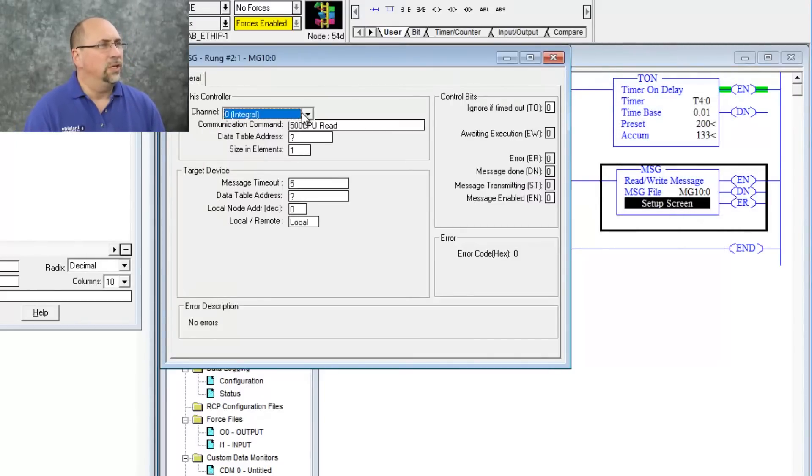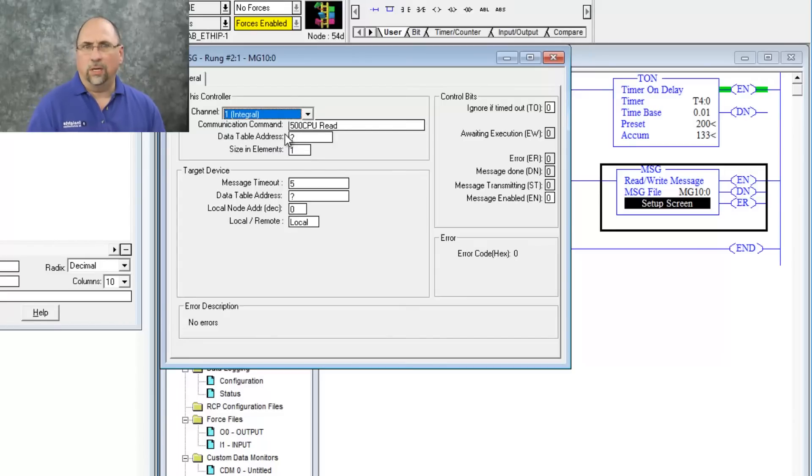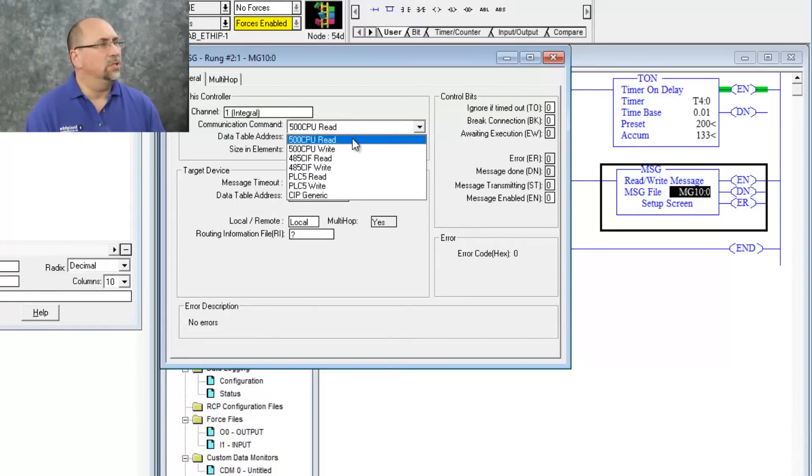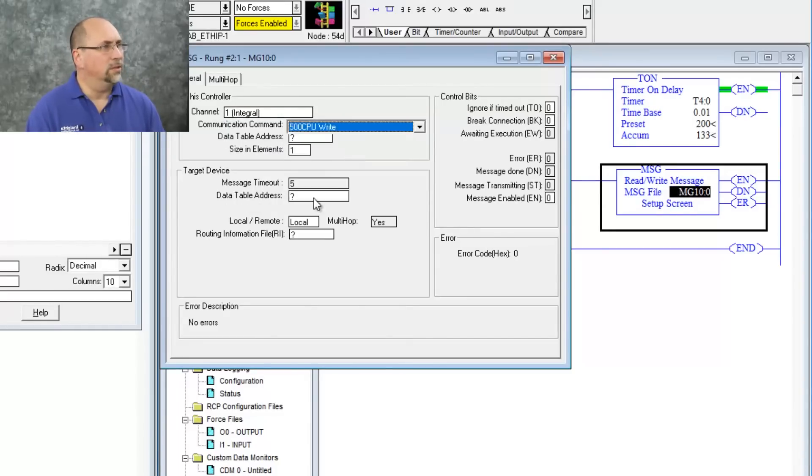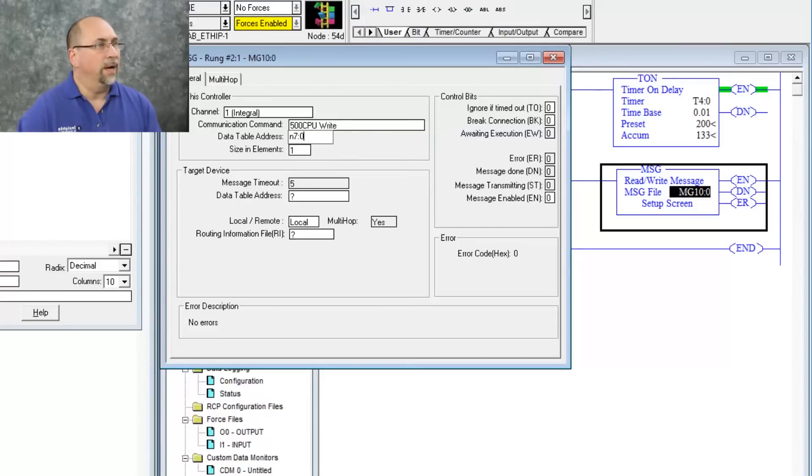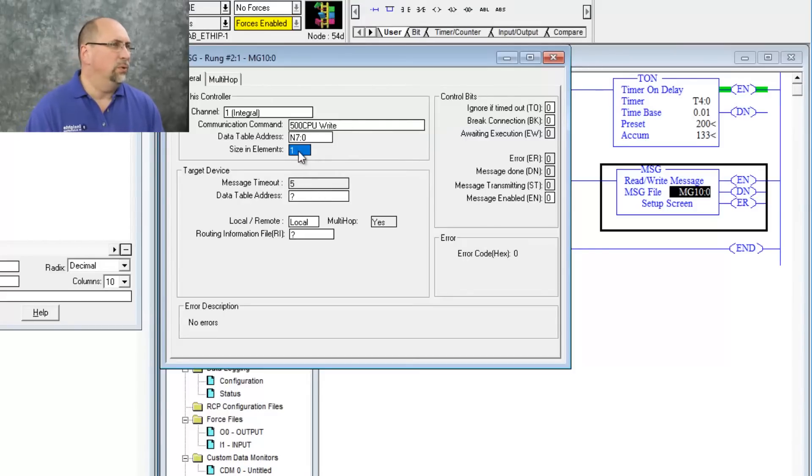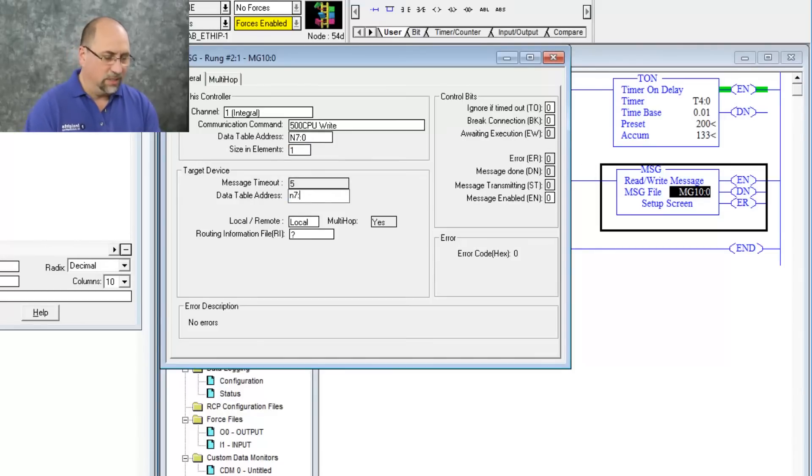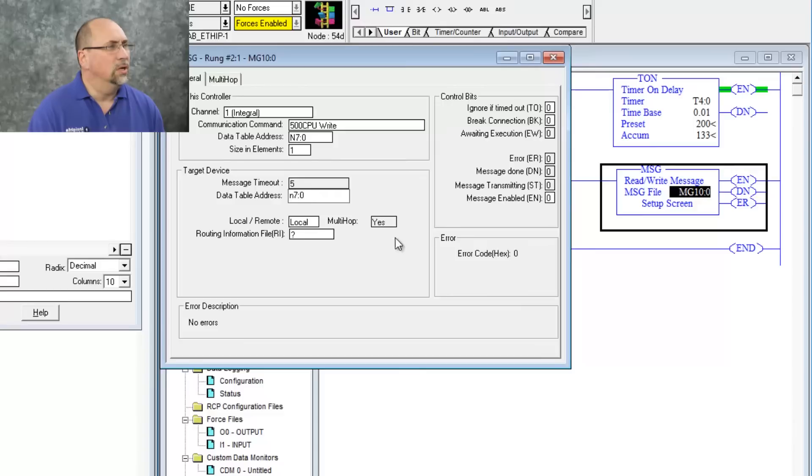I'm going to send it out channel one, which is the Ethernet port. And then I'm going to do a 500 CPU write. Data table address I'm going to read from is my own N70. We'll do a length of one, and then the data table address I'm going to write to is also going to be N70. That's in the remote PLC.